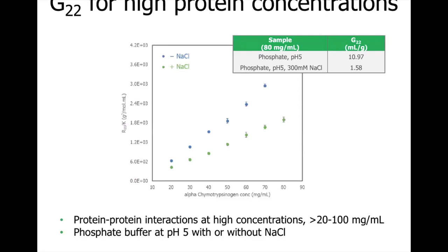B22 and Kd enable characterization of colloidal stability for protein concentrations of up to 20 mg/mL. For higher concentrations, we can use UNCLE's G22 application which accounts for molecular crowding conditions. Here we have an example of G22 data for a protein in phosphate buffer with and without sodium chloride. Strong upward trends for both conditions suggest net attractive interactions, and G22 values for phosphate buffer without sodium chloride are highest, suggesting stronger attractive forces.